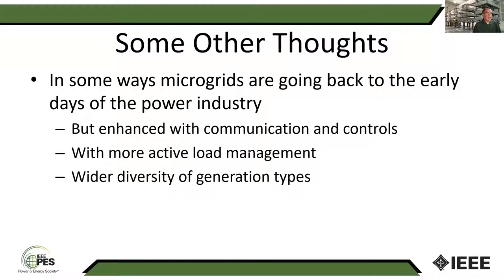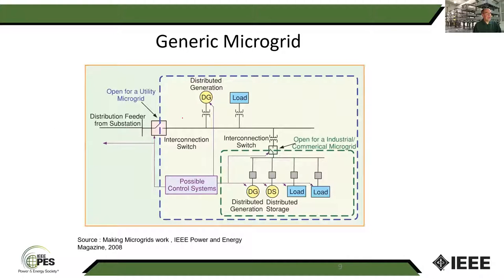But microgrids are really enhanced with a lot more communication and a lot more control than you would have seen in those traditional systems. There's often more active load management to be able to balance the generation with the load. So if you have a system that's generation constrained, then you need to have something that you can manage to have the load balanced with the generation. You're also seeing a wider diversity of generation types associated with these. So a generic microgrid is going to have one, in some cases, more points of interconnect with the utility system. So you could call this a point of common coupling or a point of interconnect. I know some people will say there's some slight differences between them, but the basic idea is that they're very similar to each other.